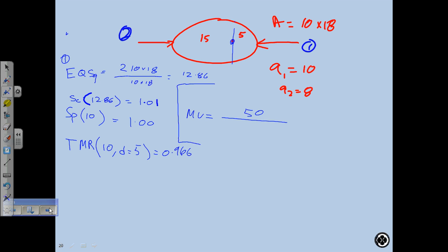Like, I didn't give you guys the thickness of the Cerrobend block. You had to calculate the transmission of the Cerrobend block, and I didn't give you the thickness, partly because I want you to remember the typical thickness. It's 7.5 cm. For cerebrum blocks, it's pretty much across the board 7.5 cm. I wanted to see if you remember that, but it's okay if you put in just an arbitrary number. That was fine, too.